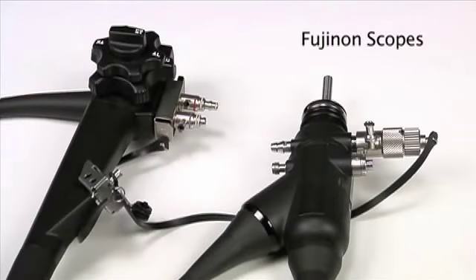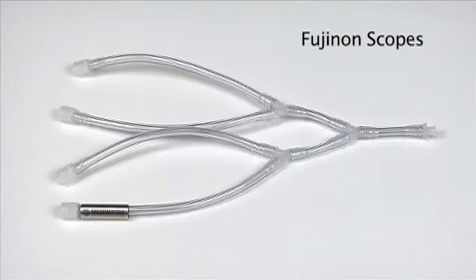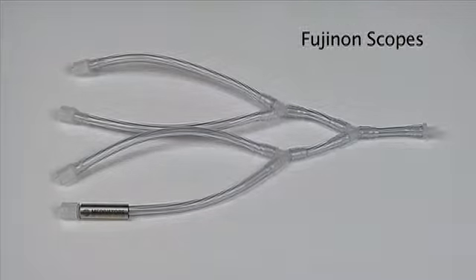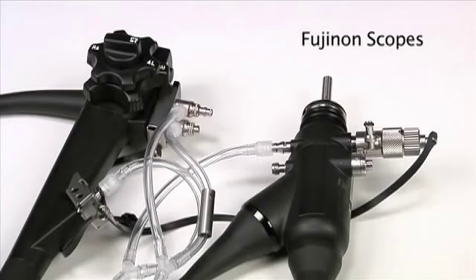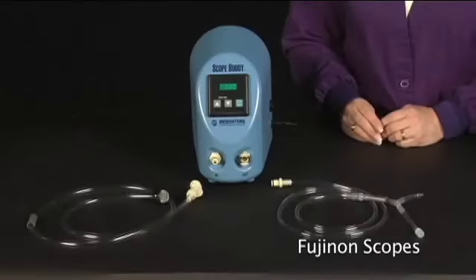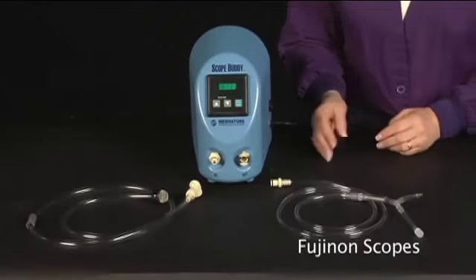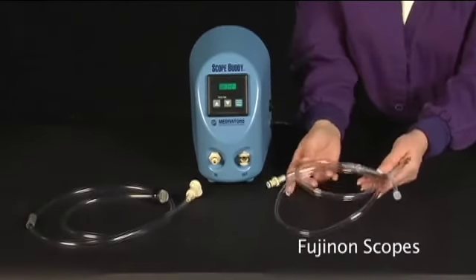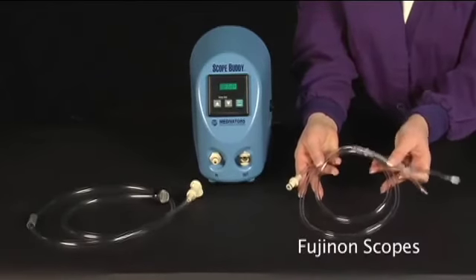For Fujinon endoscopes. To flush a Fujinon 530 series gastroscope or colonoscope, attach the Fujinon cleaning adapter to the endoscope. For endoscopes without a forward water jet or an elevator wire channel, select the Scope Buddy universal 4-way adapter and connect to the Fujinon cleaning adapter. For Fujinon endoscopes with a forward water jet, the forward water jet channel must be flushed separately from the other channels using the elevator wire channel hookup. Also, for Fujinon duodenoscopes, the elevator wire channel must be flushed separately from the other channels using the elevator wire channel hookup. First, flush all other channels using the Fujinon cleaning adapter attached to the appropriate universal cleaning adapter.